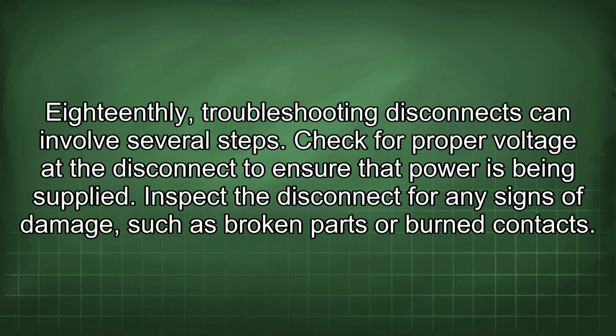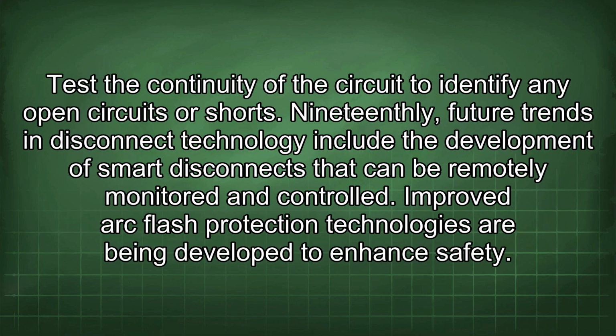18thly, troubleshooting disconnects can involve several steps. Check for proper voltage at the disconnect to ensure that power is being supplied. Inspect the disconnect for any signs of damage, such as broken parts or burned contacts. Test the continuity of the circuit to identify any open circuits or shorts.